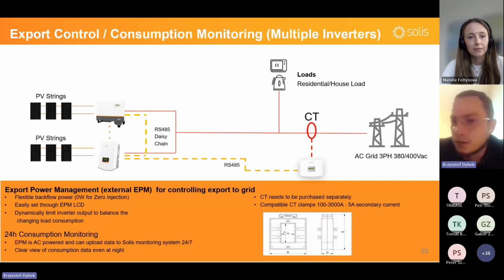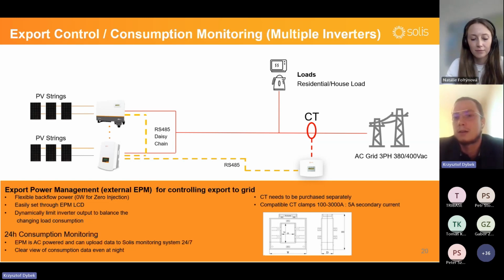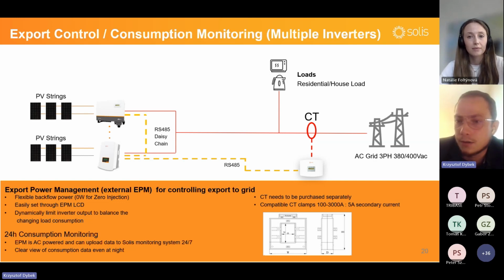EPM customers needs to buy correct current transformers. Which is correct, of course, depends of your cables on site, because you need to have a window, as we call space, inside the clamp, and make sure the clamp will close and wrap around your cable to measure current. Then we need to read the current ratio, which is written on your CT. It is usually written like this, 150/5. So our secondary current on EPM is 1. So if you have value like this, 150 divided by 5, you should divide this value by 5 to have 1. So on EPM, we'll set 30 to 1. I will show you a little bit later how this commissioning looks like.